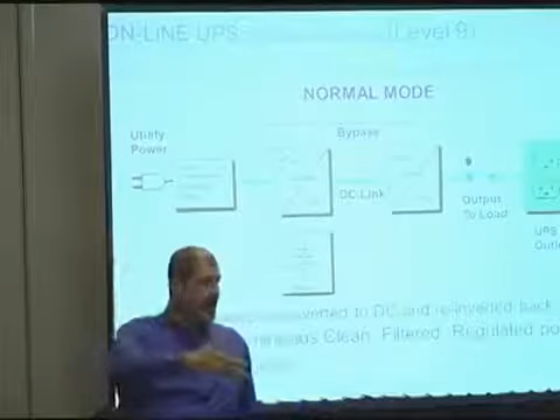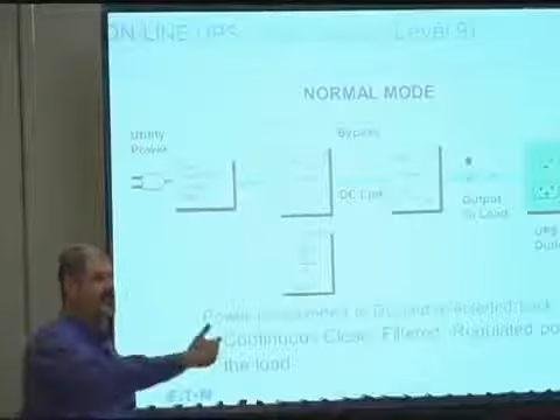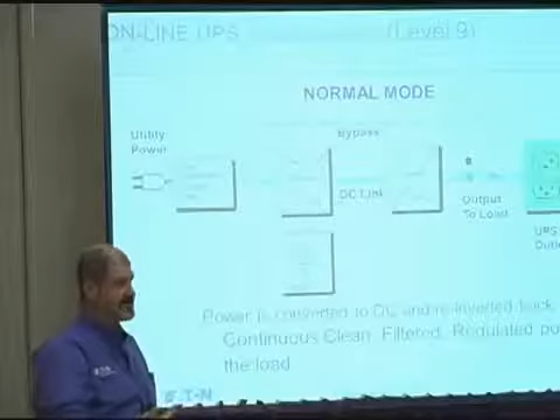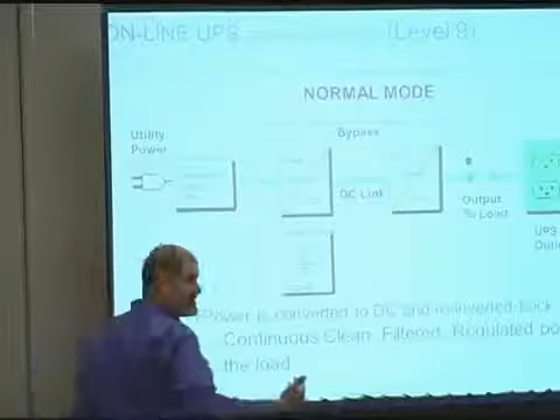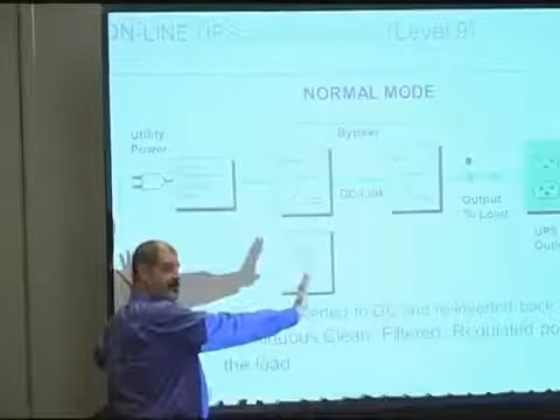The inverter regulates the output sine wave depending upon the loads, right? The loads will pull harmonic currents from the inverter, from the power source. Those harmonic currents will impact the voltage waveform created by the power supply. The output waveform will be adjusted voltage-wise to accommodate and support those harmonic loads coming in, to reduce the voltage THD to less than 5%. Now that is adjustable on some models, but really less than 5% voltage THD is typically in better than anywhere up here. That's on the load side.